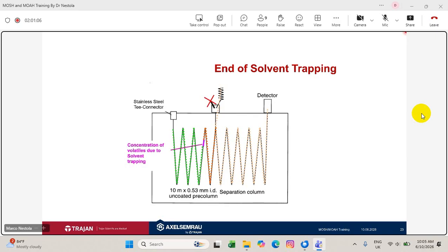Typically, you are not losing alkanes, but it was the case, unfortunately. It was also very difficult for them to check, because this observation is only made in a large volume injection. When they injected just one microliter, it had a nice chromatogram. But when you're injecting 500 microliters, they are losing C50.